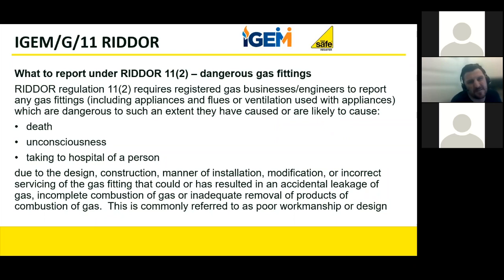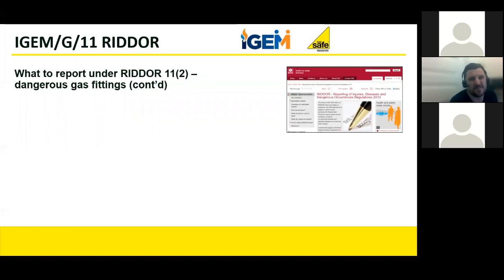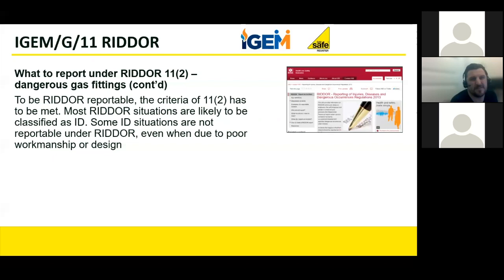So what do we report under RIDDOR 11.2? Well, it's got to meet the criteria we've just read out. And most, as I've just said, are likely to be ID situations. There are a few ID situations that might not be reportable under RIDDOR, even when down to design. And that is, again, dependent on the sort of bespoke risk assessment on site, comparing it against the requirements of the RIDDOR legislation. So an example I could think of here would be a small gas escape in an outside meter box. We'll say, for argument's sake, a 3 millibar escape.